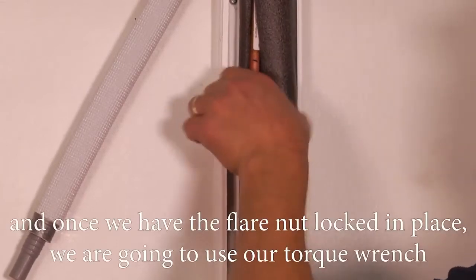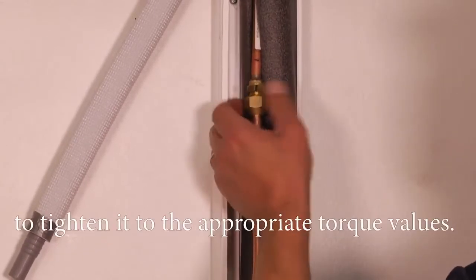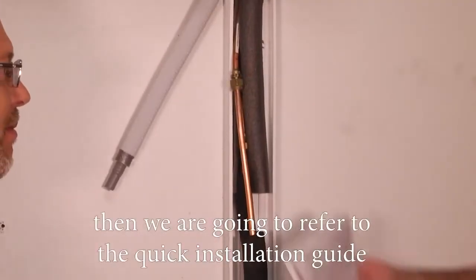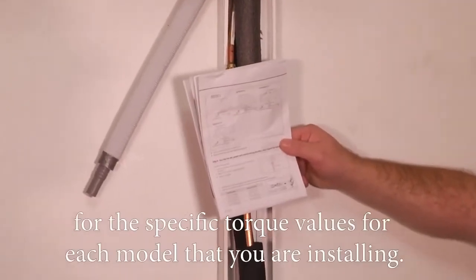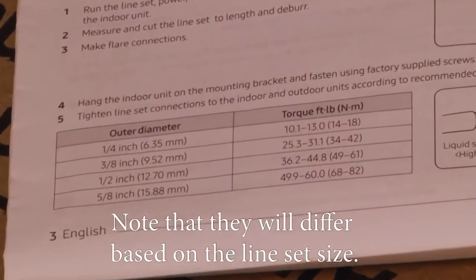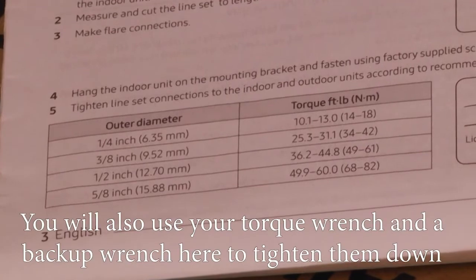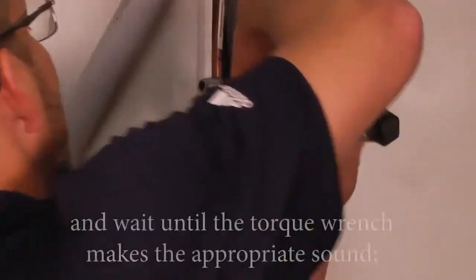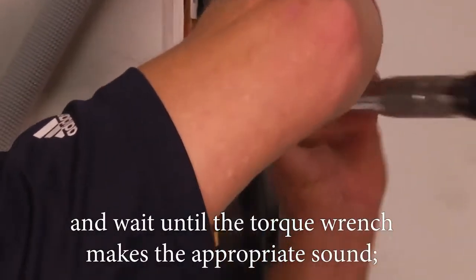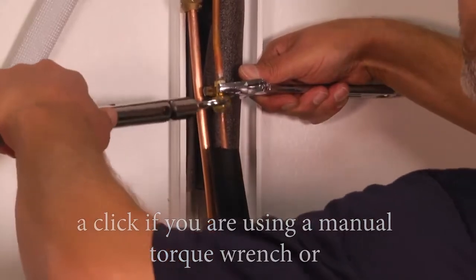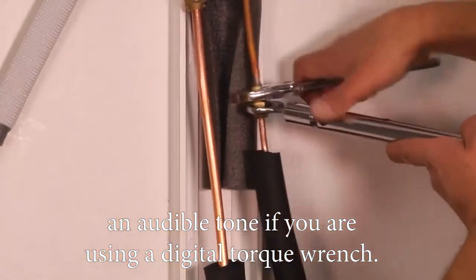And once we have the flare nut locked in place, we're going to use our torque wrench to tighten it to the appropriate torque values. Then we're going to refer to the quick installation guide for the specific torque values for each model that you're installing. Note that they will differ based on the line set size. You'll also use your torque wrench and a backup wrench here to tighten them down, and wait until the torque wrench makes the appropriate sound. A click if you're using a manual torque wrench, or an audible tone if you're using a digital torque wrench.